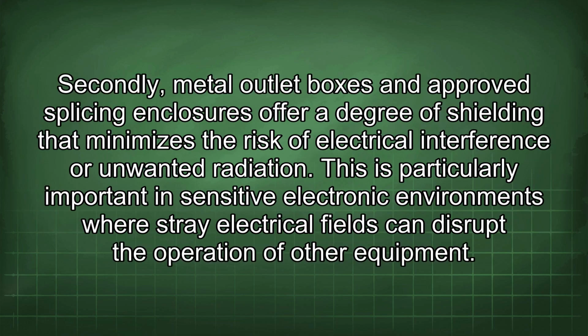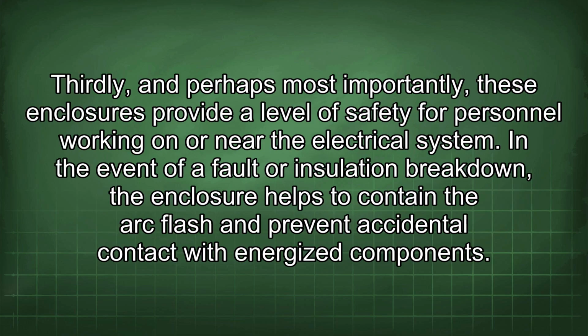Secondly, metal outlet boxes and approved splicing enclosures offer a degree of shielding that minimizes the risk of electrical interference or unwanted radiation. This is particularly important in sensitive electronic environments where stray electrical fields can disrupt the operation of other equipment. Thirdly, and perhaps most importantly, these enclosures provide a level of safety for personnel working on or near the electrical system. In the event of a fault or insulation breakdown, the enclosure helps to contain the arc flash and prevent accidental contact with energized components.